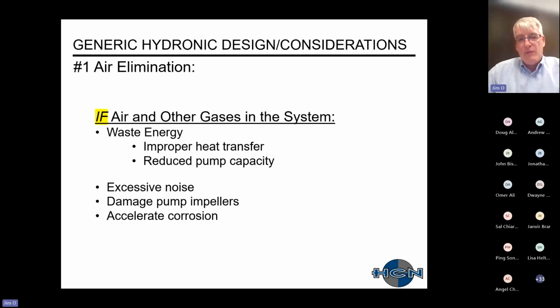Other things that will happen, what to me is the most indicative item to show that you do have a problem with air and other gases in your system is that you'll hear excessive noise throughout your piping system. You'll hear it at your pumps. You'll hear sounds like marbles are traveling through your piping, et cetera. So it will cause excessive noise.